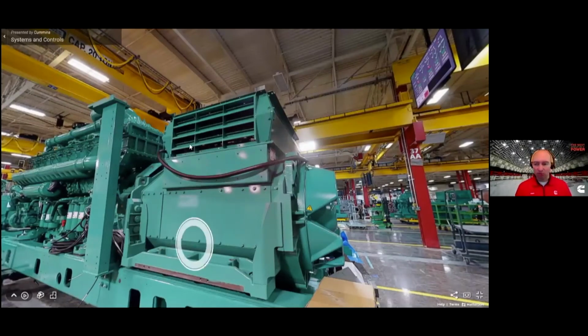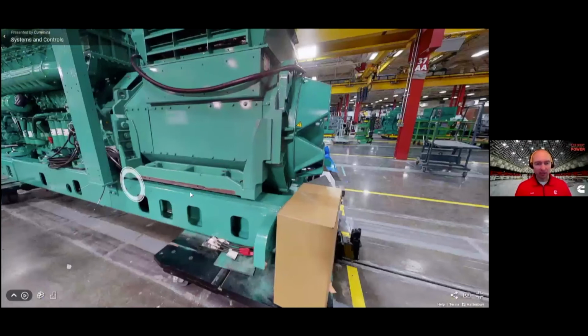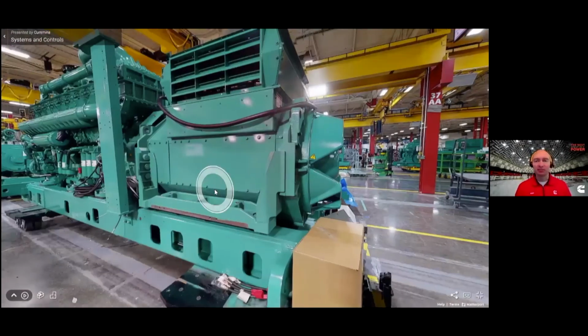It's got a nice rollback feature here — wheels that will bolt to this design, because at some point in the product's life, bearings and a flexible drive coupling bolted to the flywheel need to be serviced. That's a good while away from when it's new, but it allows servicing of the machine without needing a mechanical room with a crane, which really helps reduce the installed cost for our customers.